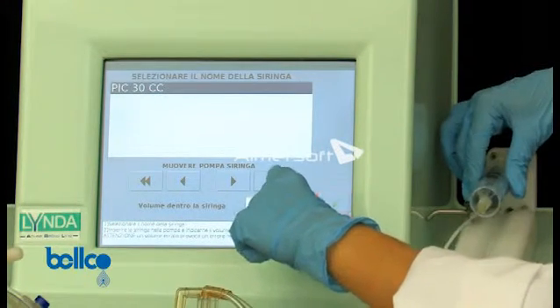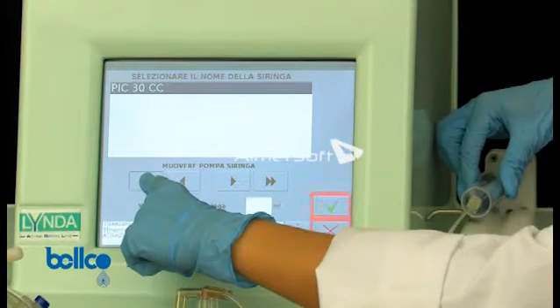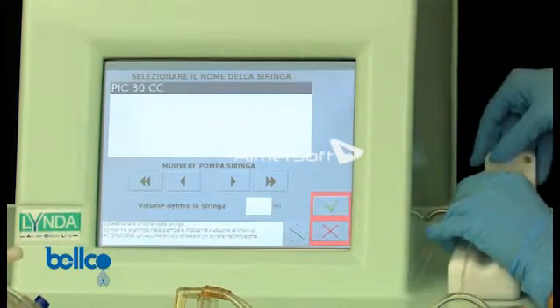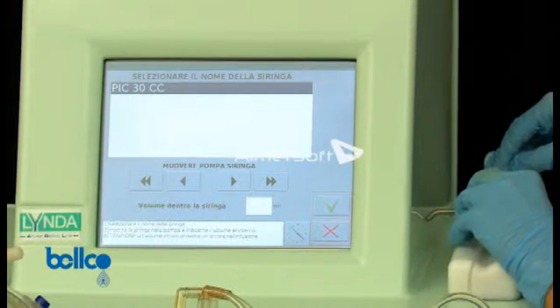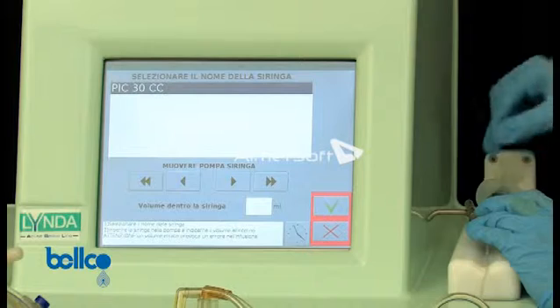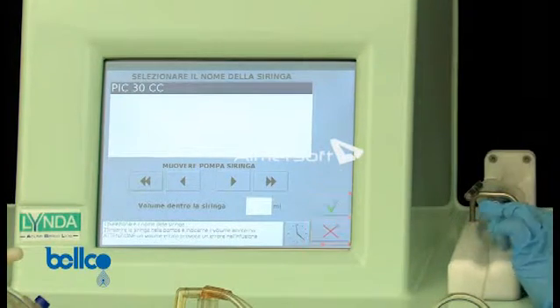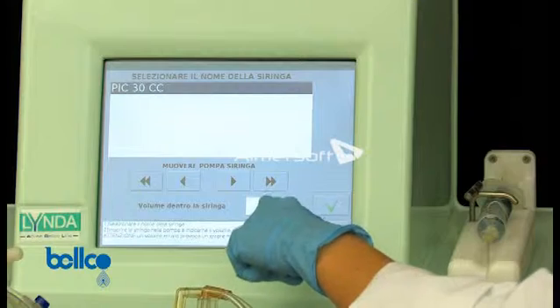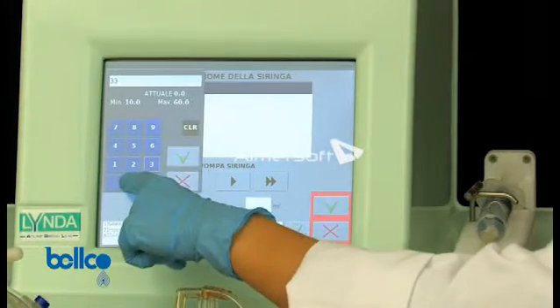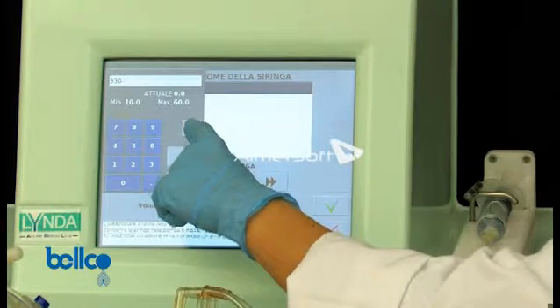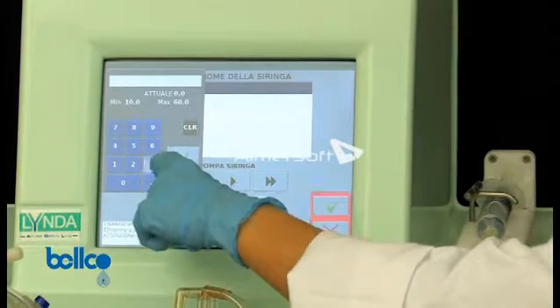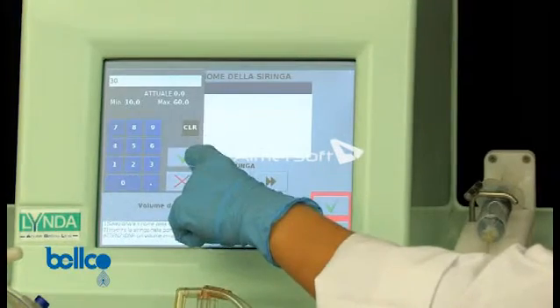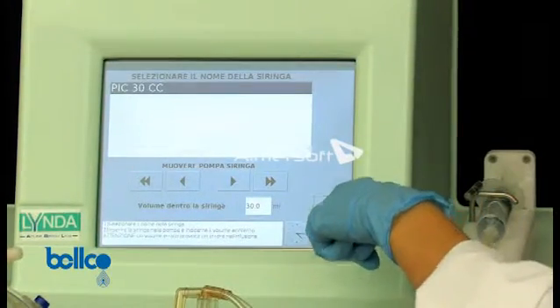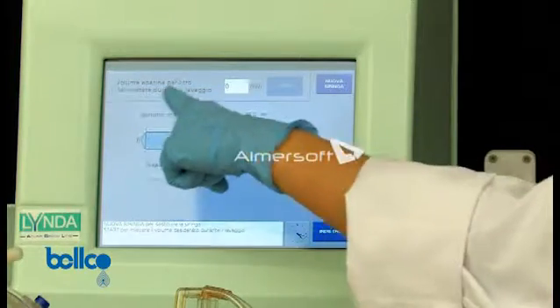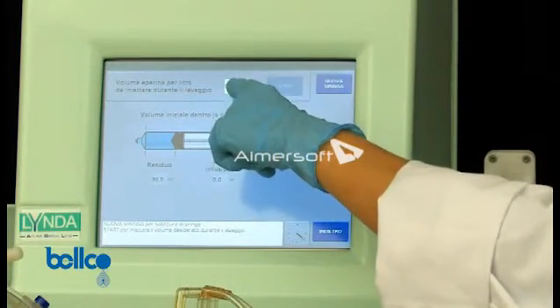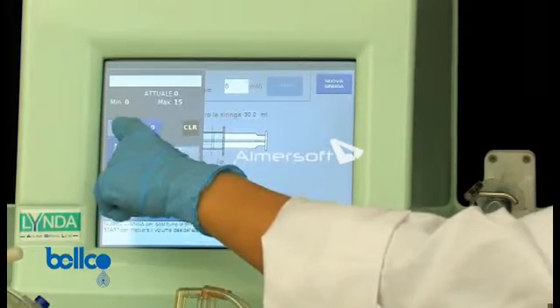Move the syringe pump carriage by tapping the arrows as shown on the screen. Accurately and securely fit the syringe into place. Lock the syringe with a dedicated support. Enter the total volume contained in the syringe and confirm twice. Then, enter the volume you want to use to rinse the circuit during priming.